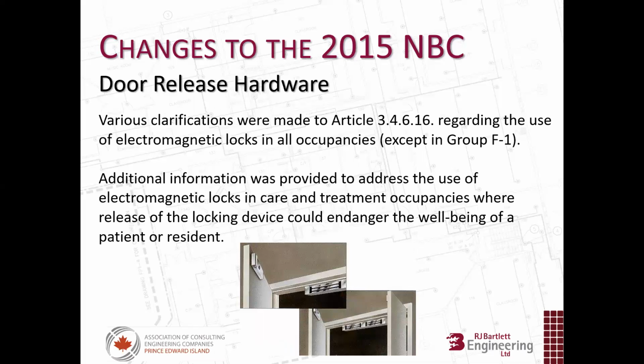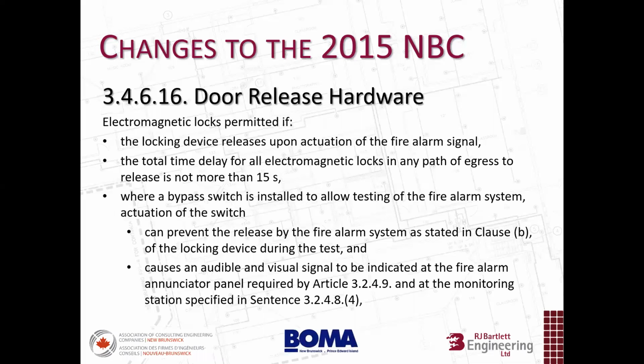So we have some clarifications on mag locks here. Except in Group F-1. Additional information was provided to address the use of electromagnetic locks in care and treatment occupancies where release of the locking device could endanger the well-being of a patient or residents. We have instances in these care occupancies where a lot of these mag locks are being used to somewhat contain patients or elderly occupants to certain areas, and during testing or maybe false activation of the fire alarm, a release of these mag locks could result in injury to these occupants, who may find themselves in areas of the building that they shouldn't be.